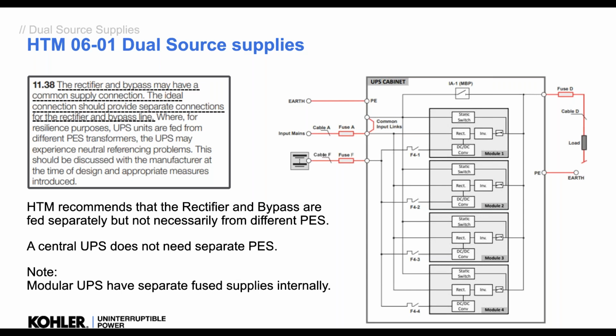And this is very much the difference between a central UPS and a final circuit. What's worth noting is it doesn't have to be from a separate supply. When it comes to a central UPS, you don't need a separate supply. And if you have a modular UPS, like in this case, we have one supply and we split it out inside, and it's protected with fuses between the rectifier and the bypass anyway. So we're actually giving it a dual source supply inside.